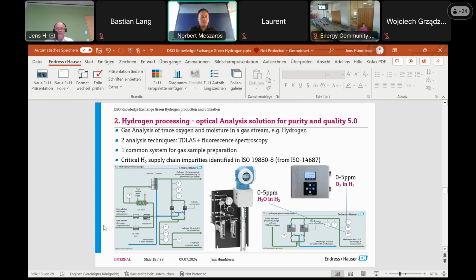This is a very robust device, shown right in the middle. We had a test project in Austria where we made a comparison against chilled mirror dew point measurement. You can use this concentration measurement also for dew point, because this is only a calculation.